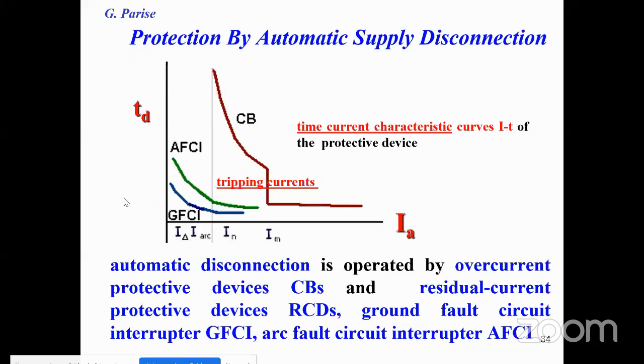Let me show, it is very important to consider the time-current characteristic curves. The curves are very important to consider. We can see the circuit breaker curves, and you have to note that the tripping currents are for high values of current, higher than the rated nominal value of the current of the circuit protective device. For low values of current, the ground fault circuit interrupter or residual current protective device is very important.